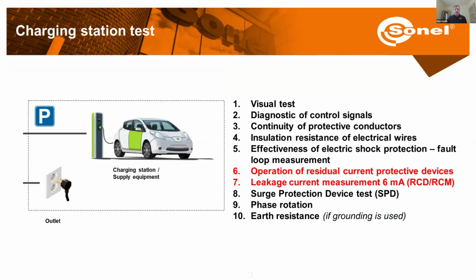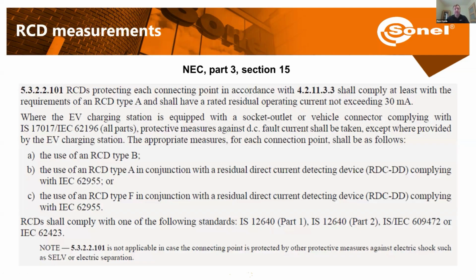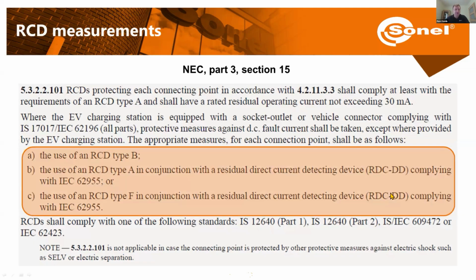Okay, then the next tests will be the operation of residual protection devices, so the RCDs, and checking leakage currents above 6 milliamps DC. So here, the RCM. Now, what is special about charging stations for vehicles compared to a regular electrical installation is that the National Electrical Code requires us to use an RCD of type B, or type A with additional protection against leakage currents above 6 milliamps DC, or an RCD of type F, again with additional protection against leakage currents above 6 milliamps DC. This additional protection needs to comply with the international standard IEC 62955.